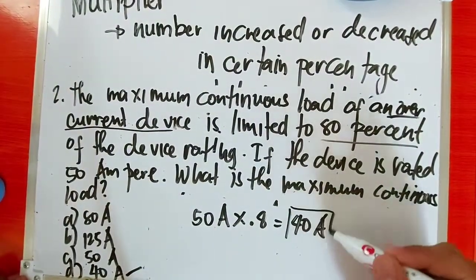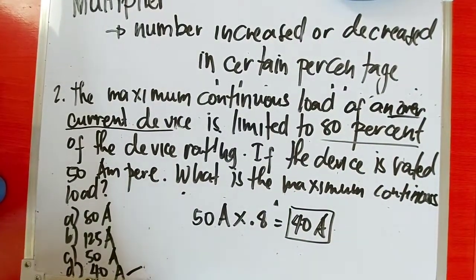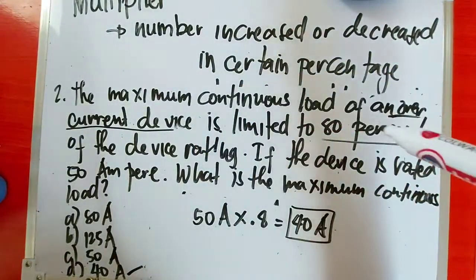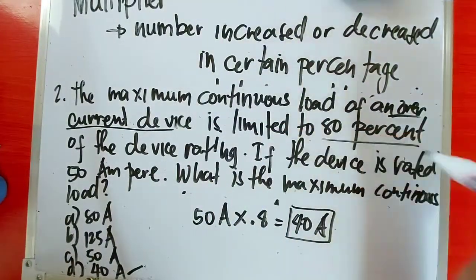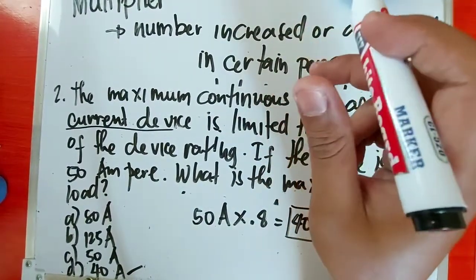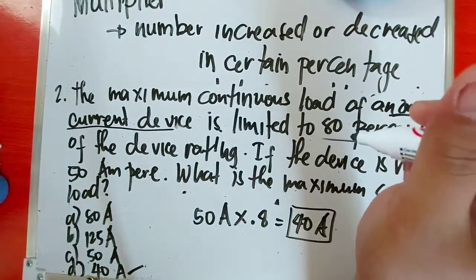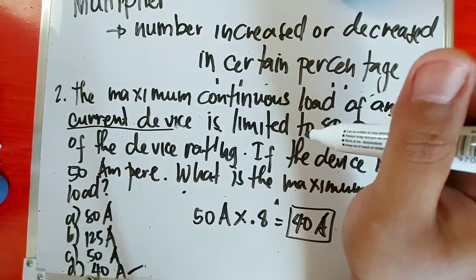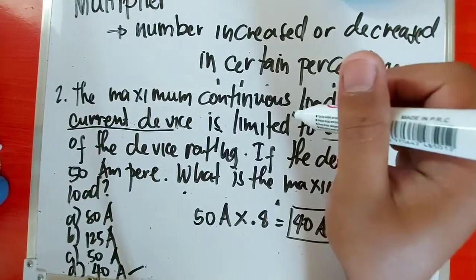Okay, so that's how easy it is to solve multiplier problems. Just remember, when it's maximum continuous load of an overcurrent device, it's limited to only 80% always. The 125% we mentioned earlier is when you're sizing your protection, your circuit breaker. Okay? If it's a continuous load, it needs to be times 125%.